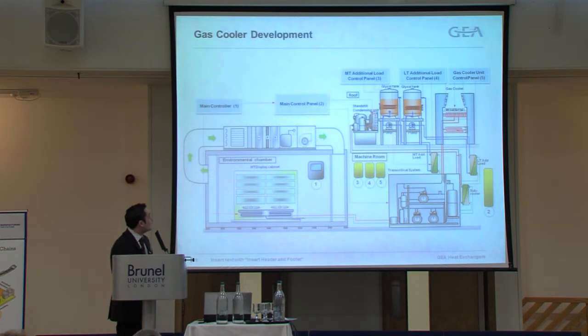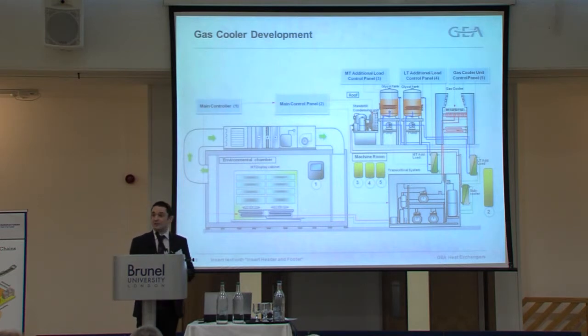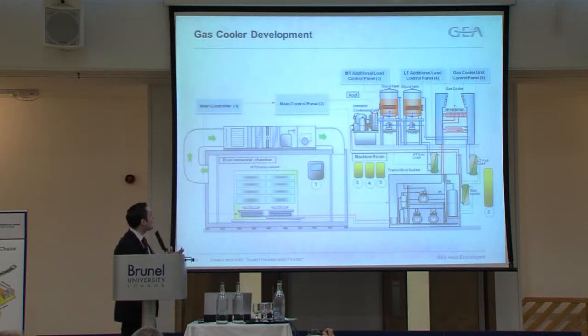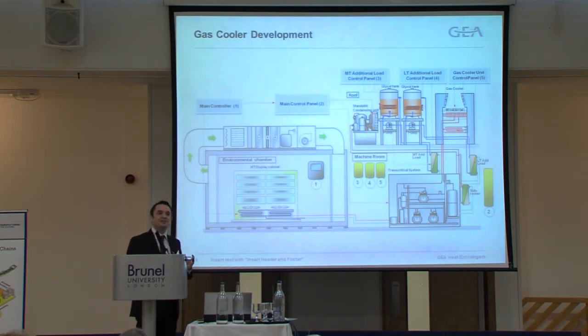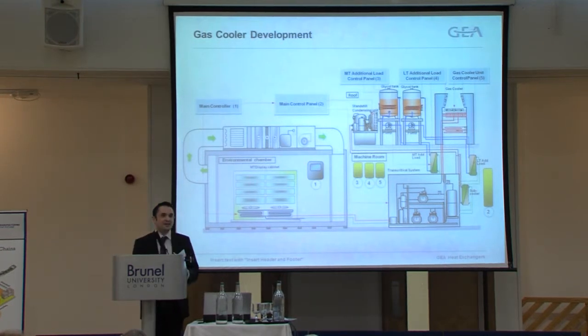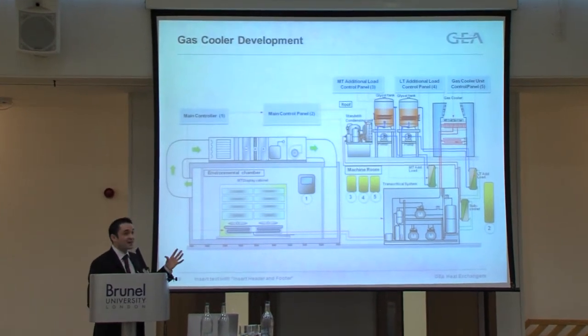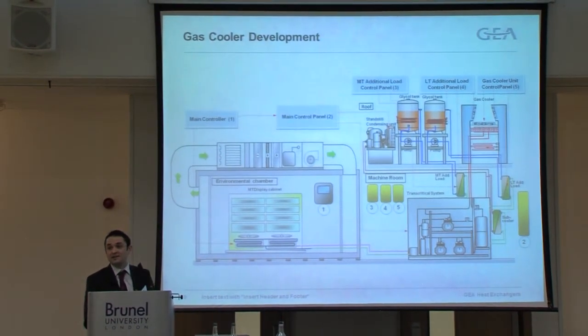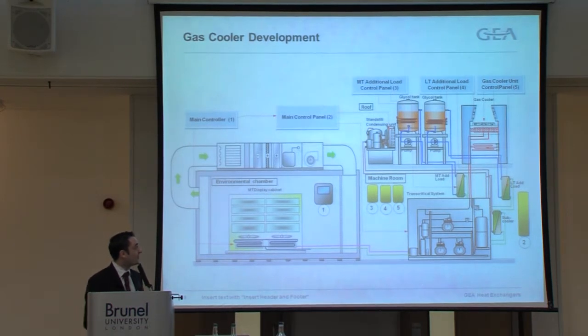So this is another graphic of the test facility. It doesn't quite look like you'd normally see in a refrigeration application or in a refrigeration installation. It's because it is a test facility. You can see there that we've got these glycol tanks here, which can allow us to vary the load that the chillers and the gas coolers are operating at. We are controlling the temperature and the humidity, therefore the loading going onto the display cases we have. This allowed us to test the gas cooler in every extreme of temperature and application we could think of. We wanted to be able to ensure that the product longevity and operation would align with the customer's expectations throughout its life cycle.